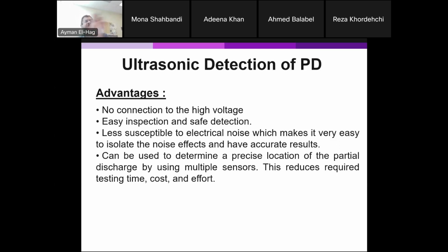Also, like the RF antenna, it can be used to localize the partial discharge source using multiple sensors. Personally, I have done that several times to localize the partial discharge inside the transformer, and it is very effective. One big advantage of the acoustic compared to the RF: if I want multiple RF sensors, I have to have the pre-arrangement in the transformer tank, because I can't insert multiple RF antennas if they don't already exist. But with the acoustic, you don't need to do that. Because they come as a piezoelectric material, you attach it to the tank, and usually there is a magnet to hold it. You can take it off or add it. So the system can be used to inspect a transformer, having multiple sensors at different locations, measure the signals if there are any, and try to localize the partial discharge. It's very good in that aspect, and it's completely non-intrusive.